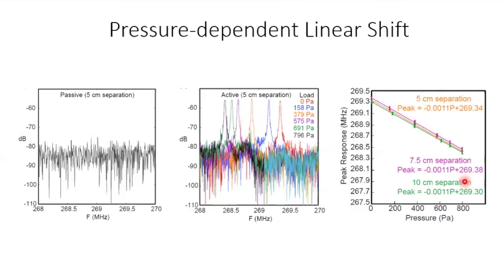This is very sensitive because 1.1 kilohertz is much larger than the peak width of the resonance frequency curve. As a rough estimate, we expect the sensor to be able to reliably measure pressure changes as small as 27 Pascal. This is already approaching what can be achieved by wired technology.